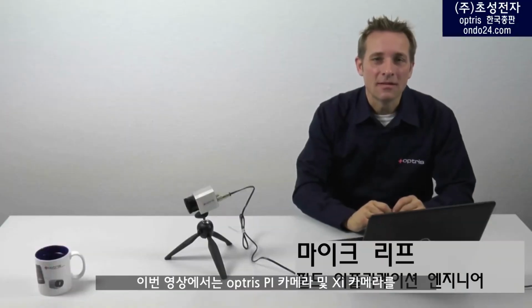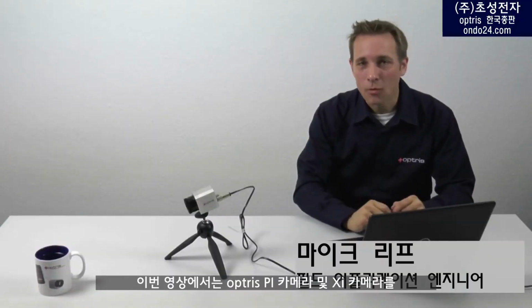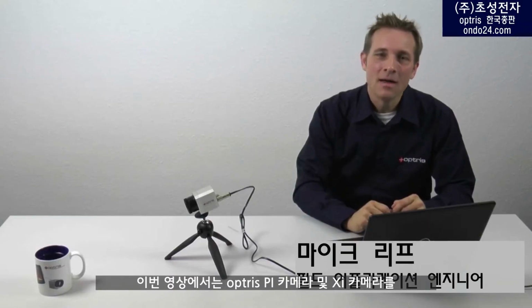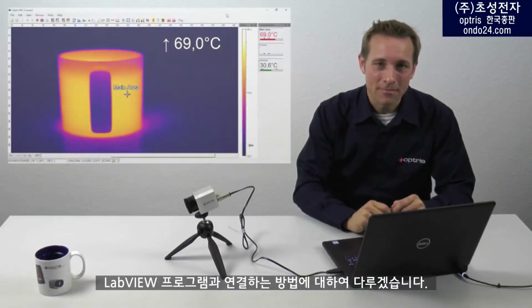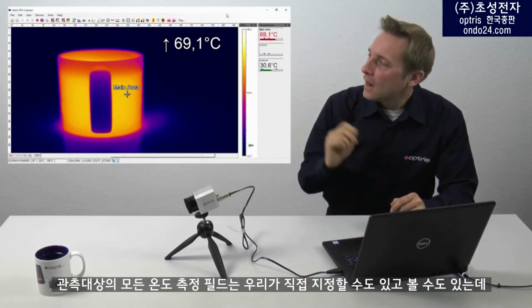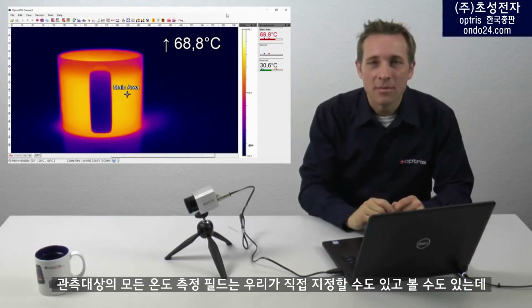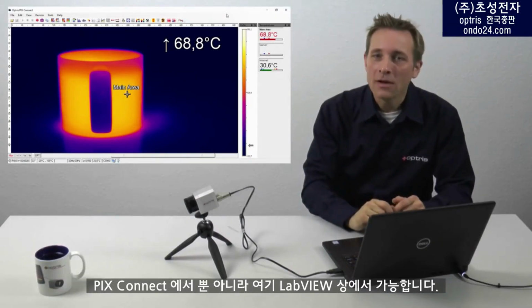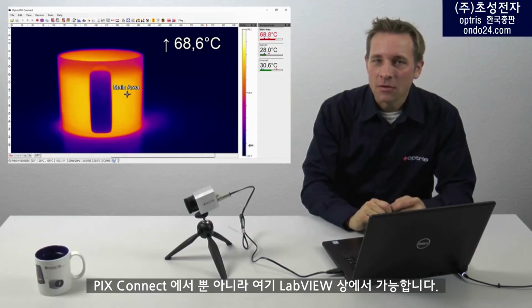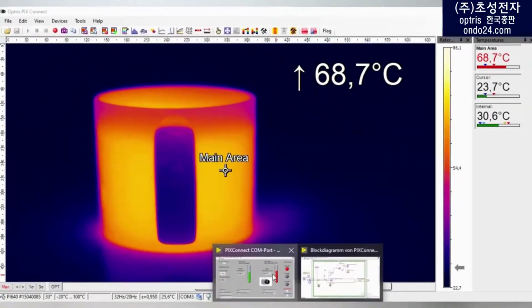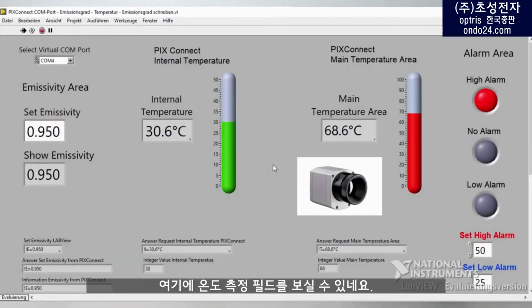In this video, I'm going to show you how to connect the Optris PI camera, or also the Optris XI camera, with the LabVIEW environment. The objective is to be able to display all the temperature measurement fields that we can create with the PIX Connect software, also in LabVIEW. Here, for example, you can read out temperature measurement fields, which represent the camera internal temperature, or also set values such as the emissivity.